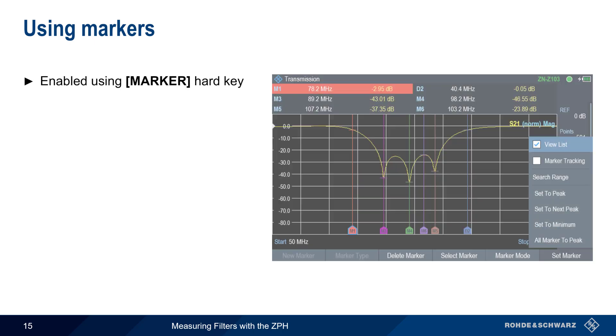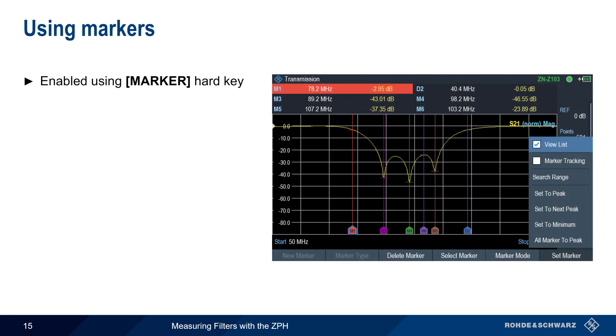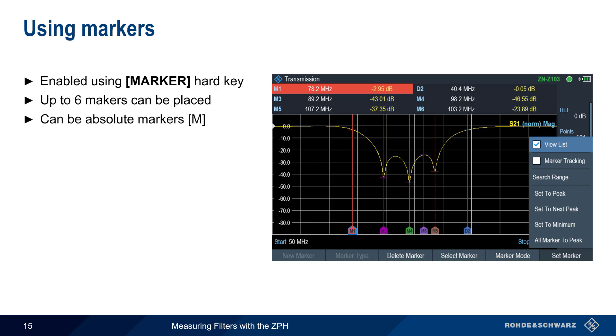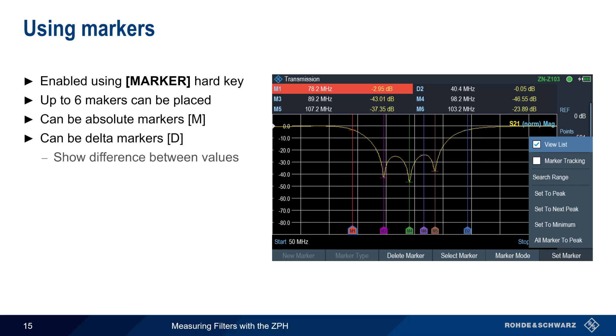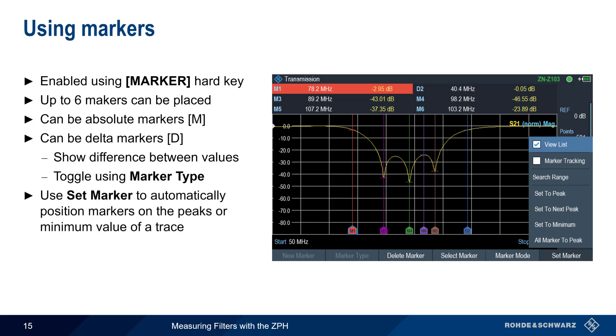Markers are enabled using the Marker hard key and can be used to numerically measure filter characteristics. Up to six markers can be placed on a trace, and these can be either absolute markers or delta markers, which show the difference between marker values. Toggling between types is done by using Marker Type. The functions provided under Set Marker can be used to automatically place markers on the peak or minimum values of the displayed trace.